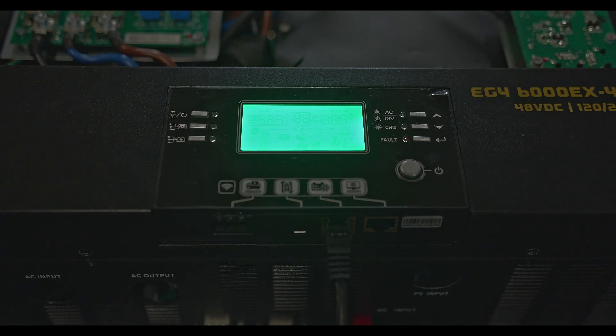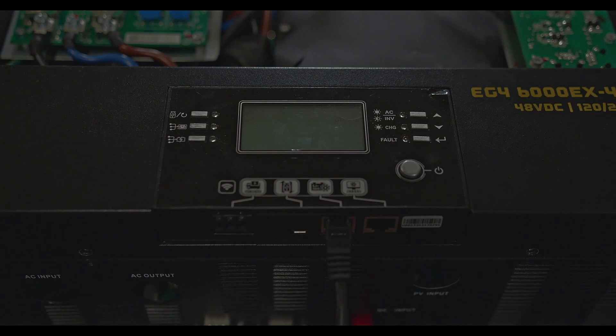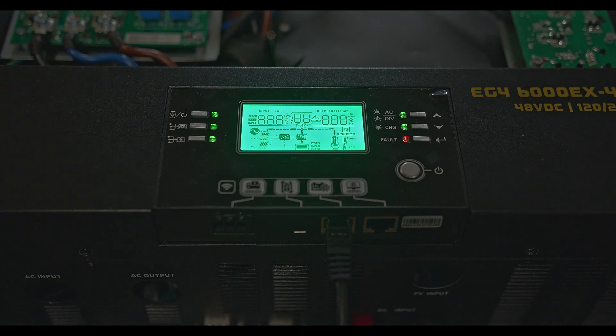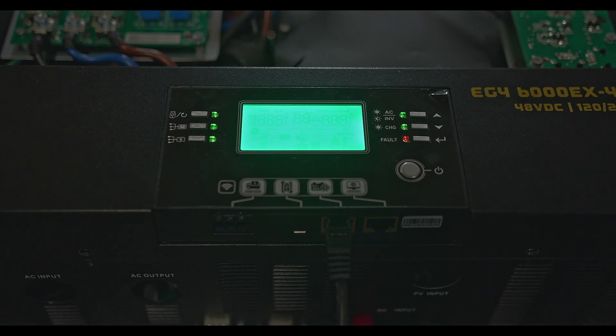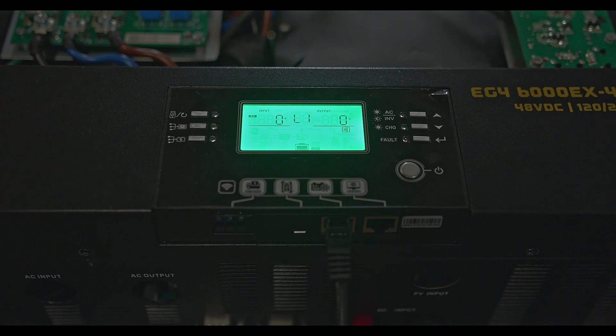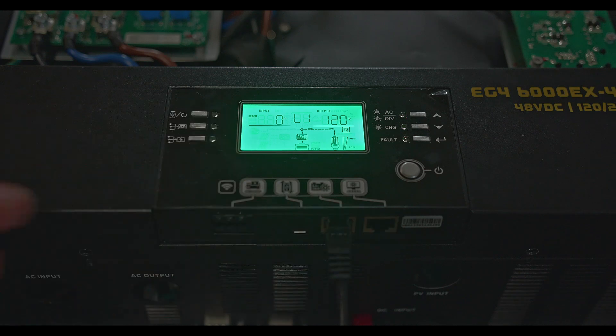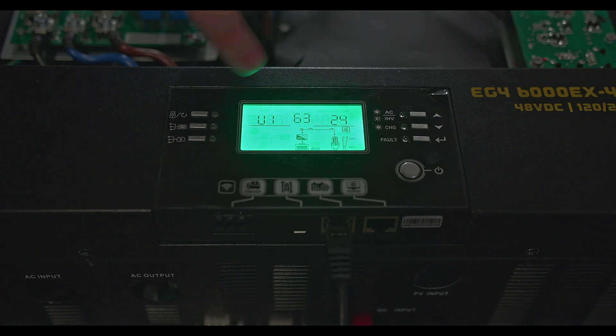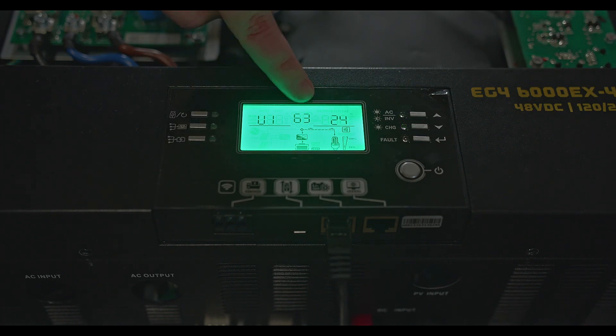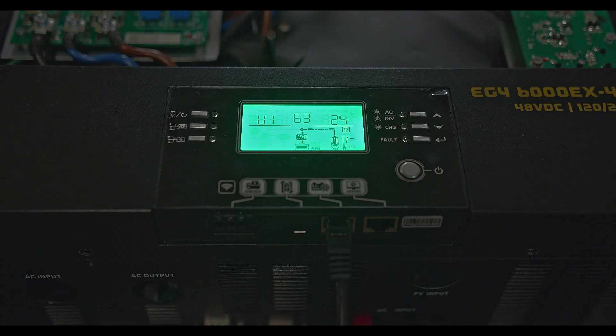Let's let it count down. Now error 32 is cleared, we're good to go. If you still have error 32, it's usually because you have that cable plugged in so make sure that's removed. If you press up you'll see display 61.15 and now we've updated our inverter to 63.24. Now we're good to go. Thank you so much for watching, we'll see you next time.